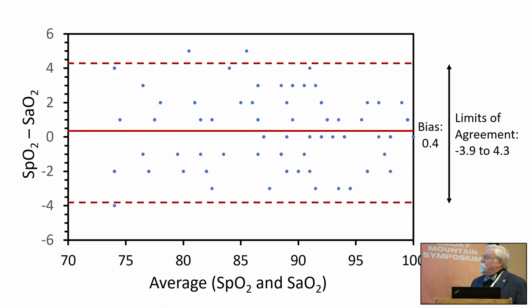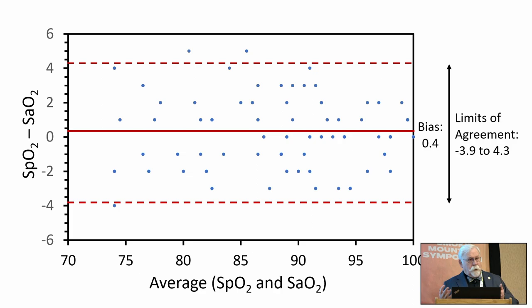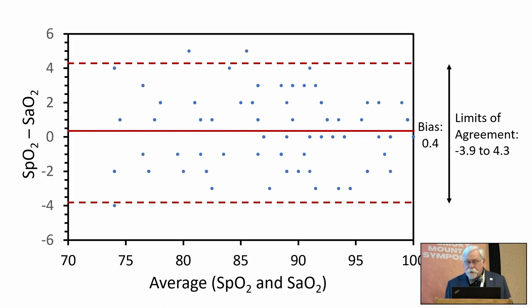You can display this data on a Bland-Altman type graph where the y-axis shows the difference between the pulse oximeter and co-oximeter, and the x-axis shows the average of the two measurements. The bias on average is close to zero - so on average the pulse oximeter and co-oximeter are about the same. However, the limits of agreement, which matter most for accuracy, are about plus or minus 4%, which is typical for the pulse oximeters we all use every day.